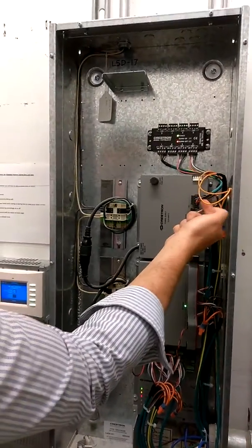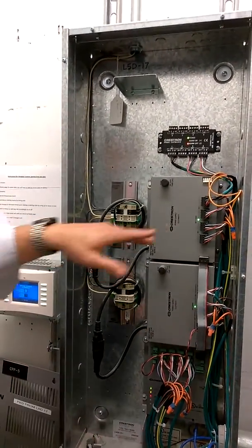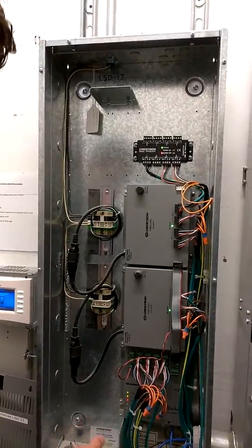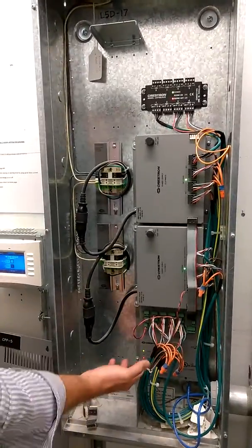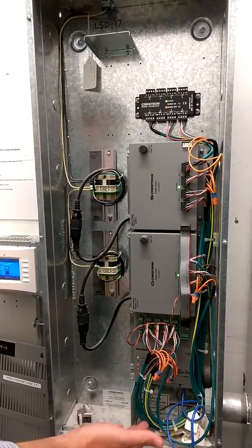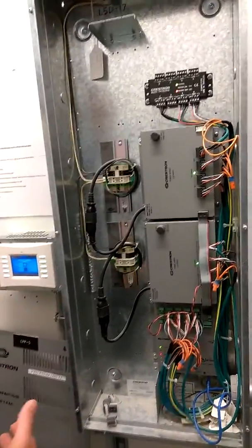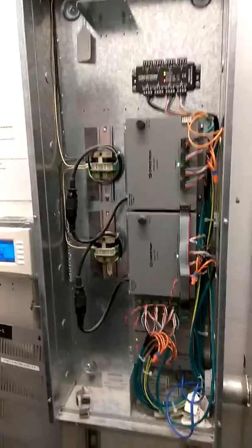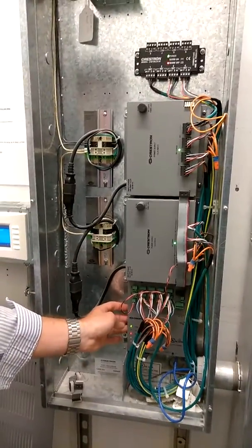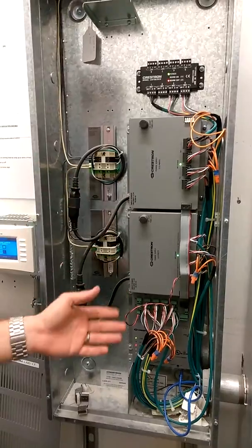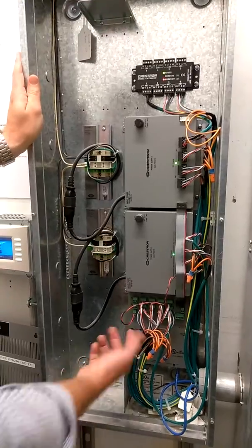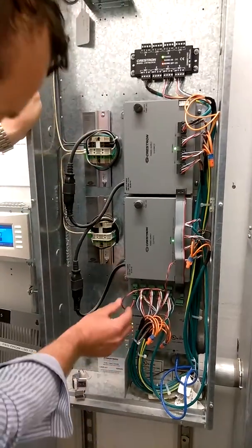And as you see, you can parallel these things. So basically, this wire here can go into a keypad, and out of that keypad can go into another keypad, and that's how the communication happens across the floors. This device is a computer, and it runs 24/7. It's not as high tech as a laptop, obviously, but it's an old control processor. So if something is going on, or something's frozen, or the lights aren't turning off, you can come in and reboot these devices.